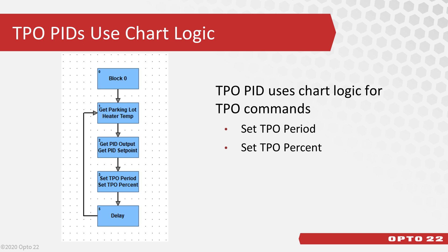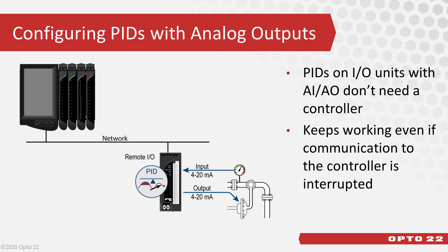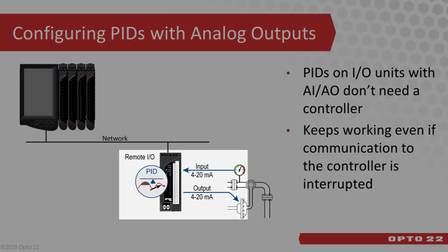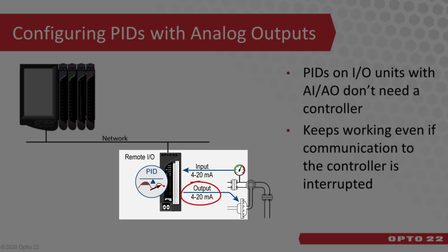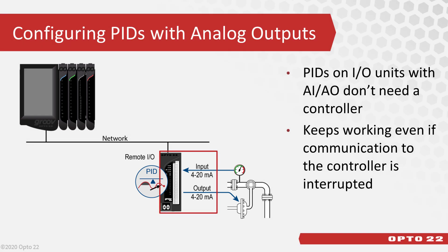Because of the way we'll be setting up the PID, we'll have to add a chart in the strategy with control logic for the PID. In this case, the PID running on the IO unit is not independent of the controller because it relies on the commands in the chart. The other type of PID is when the PID's output is wired to an analog output point. The beauty of this type is that your PID will just keep working because it runs independently on the IO unit that it's configured on. Both the analog input and analog output reside on the IO unit, and if communication to the controller is interrupted, the PID keeps working until it's manually stopped or powered down.